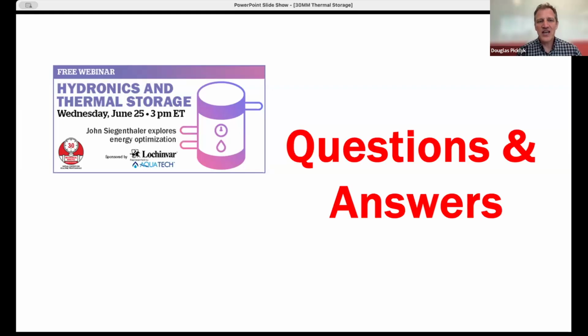Jeff is asking, how do you size the tank? And again, you could use multiple tanks if you're looking to store even more heat. Jeff, again, it's a complicated answer. The best way to get a handle on it, this is not the easy way, but it's the best way, is to have software that will literally simulate the operation of the system hour by hour, minute by minute, based on what the rates are, when the off-peak rates occur, what the house load is, and so forth.